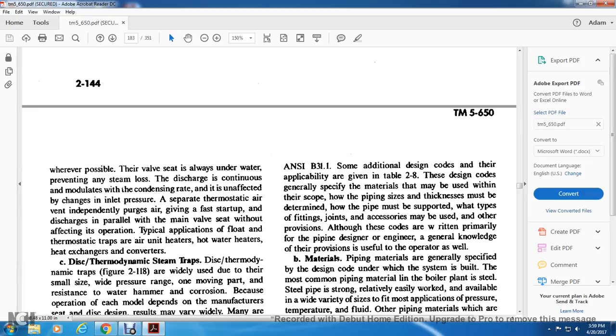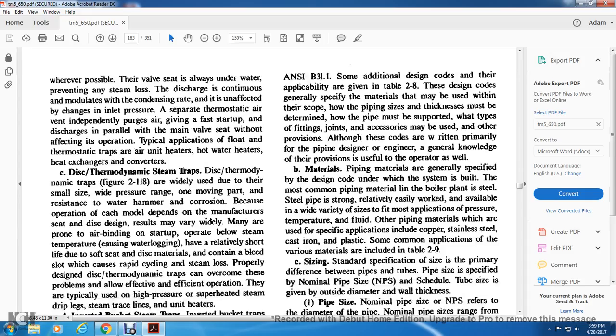Whenever possible, the valve seat is always underwater, preventing any steam loss. The discharge continues to modulate for the condensing rate. It is unaffected by changes in inlet pressure, and the separate thermostatic air vent independently purges air, keeping the startup discharge of the air separate from the main valve seat without affecting its operation. A typical application for the float thermostatic trap is the air unit heater, the hot water heater, or the heat exchange converter.